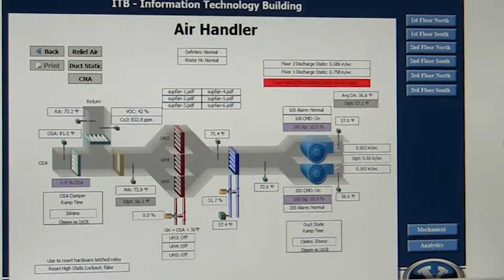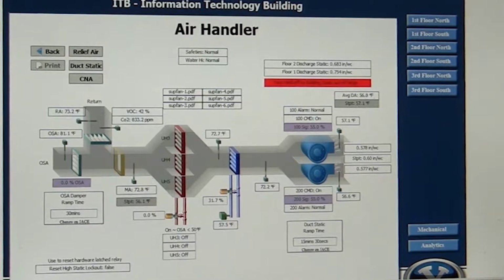So when calibrating sensors, one of the things you'll want to do is get your building or air handler into a steady state—we don't want valves opening and shutting. This time of year, we've got to have cooling.